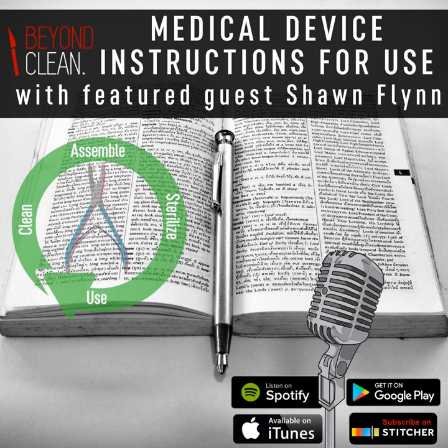But a lot of times, if they just make a change due to the FDA or their own internal ISO or quality documents, you see a lot of them moving to having their IFUs online now, so there's no paper. Technically, within their labeling requirements, if they send out paper IFUs, they're supposed to make sure a preceding rev of that IFU is not on site at that customer's hospital. So it's kind of twofold.